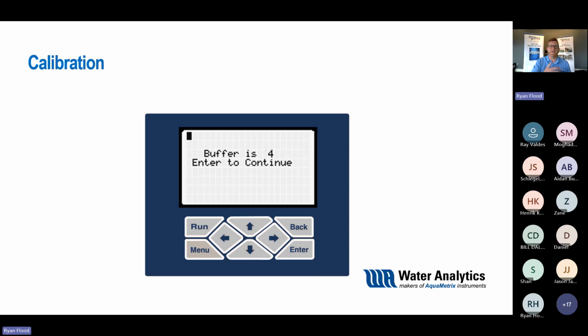But if you're putting it in and the auto detect is off, what it actually can help you do is stop the calibration process earlier and move over to the maintenance section. Because if the auto detect says you're way off, then you know that you're wasting your time performing the calibration. You have to perform some of the additional maintenance beyond just that simple cleaning I talked about earlier.